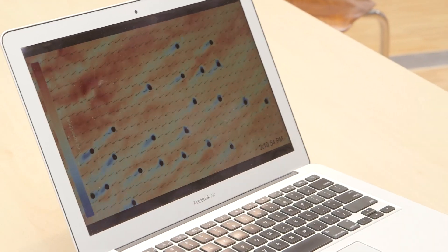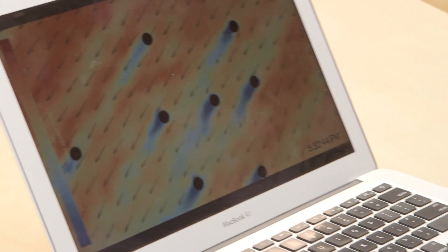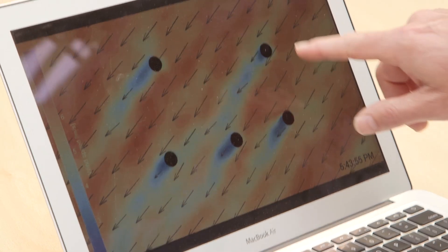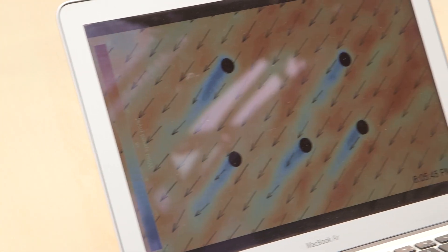You see the wind farm here — all these black dots are wind turbines. The colors represent wind speed: blue is low and red is high. The farm is producing, and you see these blue streaks behind the turbines — those are wakes, showing the slowed-down air. Right now all turbines are kind of seeing free-stream wind, and now this one is being blocked by the first one. So what we do is start easing off on the first one to create more power for the pair of them.